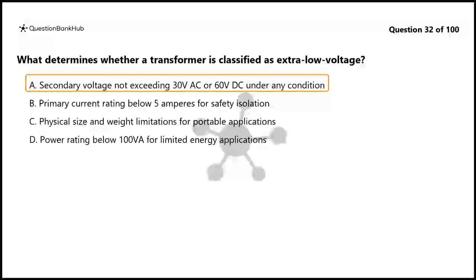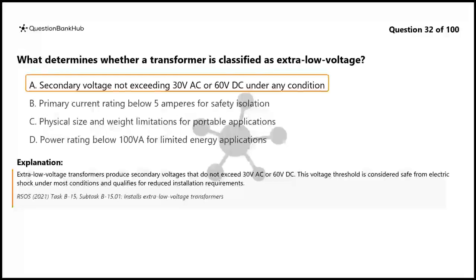The correct answer is A. Secondary voltage not exceeding 30 volts AC or 60 volts DC under any condition. Extra-low voltage transformers produce secondary voltages that do not exceed 30 volts AC or 60 volts DC. This voltage threshold is considered safe from electric shock under most conditions and qualifies for reduced installation requirements.